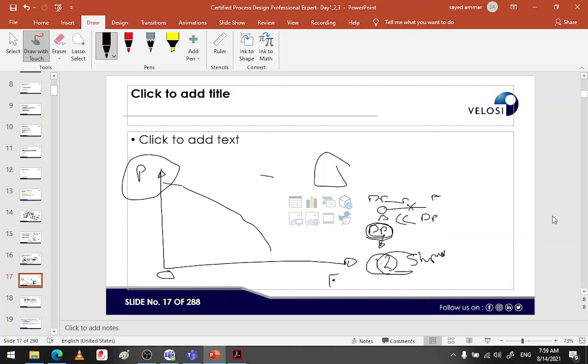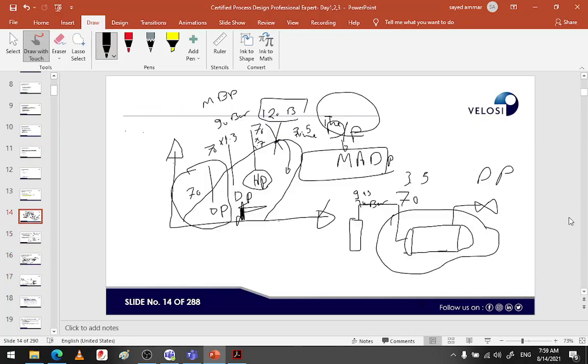Another question, please, regarding the design pressure or temperature for any component. During operation, will reaching the design pressure or temperature lead to equipment or component failure, or is it only reaching the highest pressure or temperature that causes failure? I mean, will it be okay during operation to reach the design pressure for some reasons? Do you attend this slide? Here is the point of failure. As a rule of thumb, when you reach 2 times the design pressure, your weakest point will start to leak, which will be the flanges. But when you reach 3.5 times, the equipment will rupture.